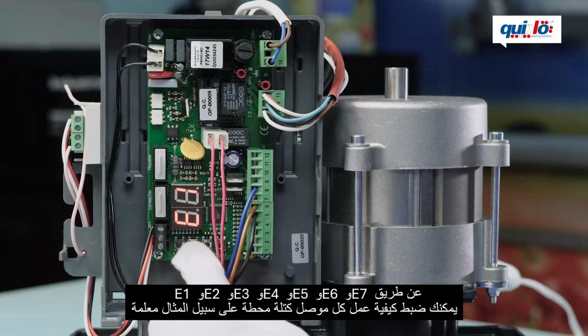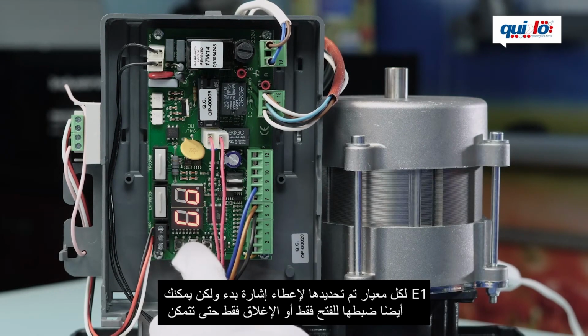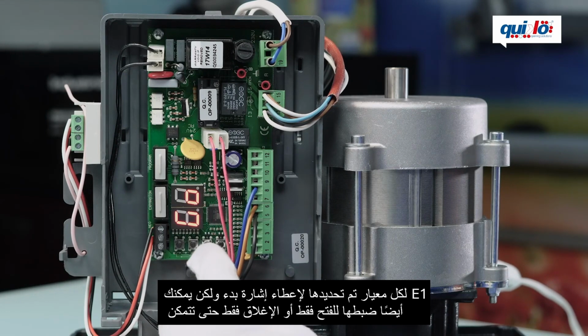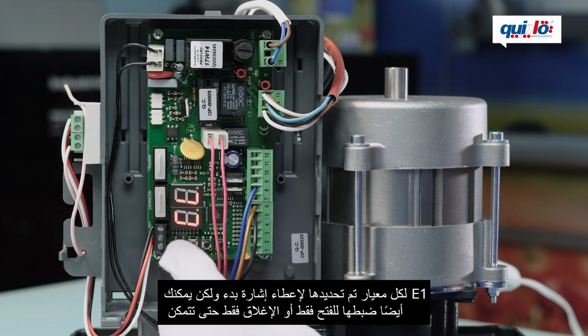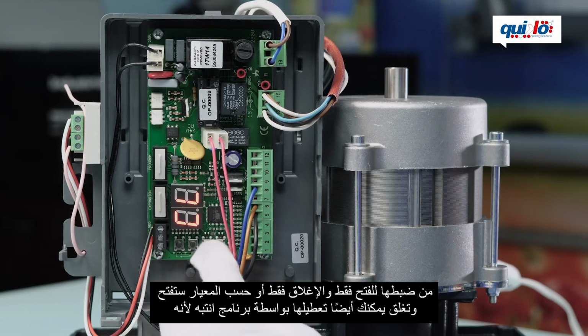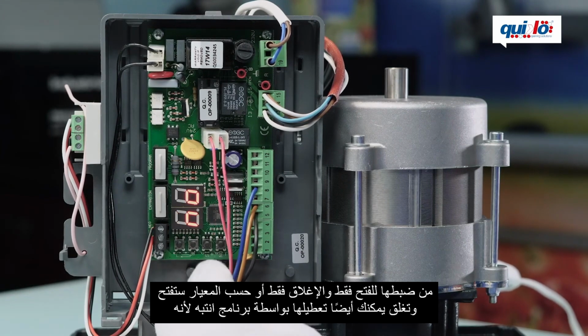connector to work. For example, E1 parameter, per standard it is set to give a start signal, but you can also set it to open only or close only. So you can set it to open only, close only, or by standard it will open and close. You can also disable it via software.